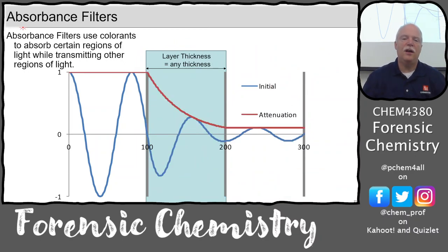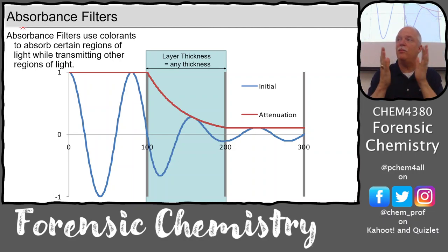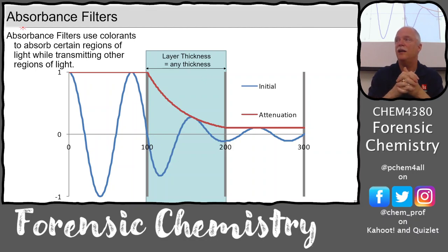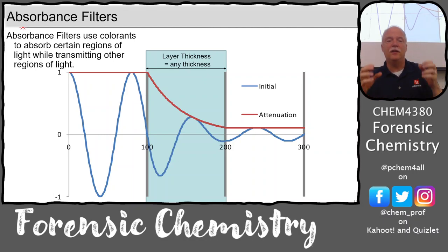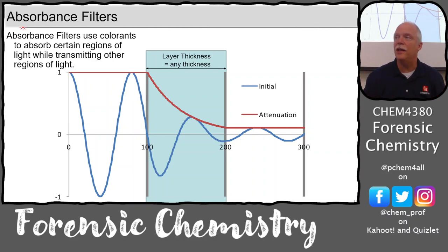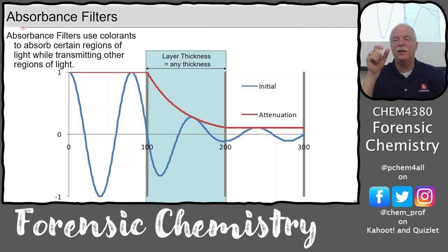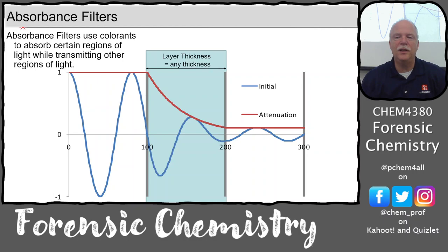In absorption filters, all the attenuated light is absorbed by the glass. With a really bright source, the absorption filter heats up and degrades over time — dye molecules in the glass get bleached out by the light eventually. So there's a shorter lifetime for absorption filters. Interference filters' thin layers can also wear out, but absorption filters definitely absorb more light and heat up more.